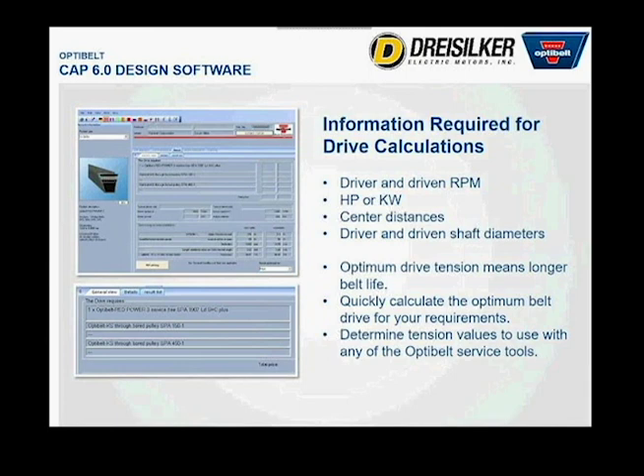Dreisilker's salesmen are able to do calculations for you. The biggest pieces of information they need are the driver and driven RPM, so your input and output, what your motor RPM is, typically 1800 or so, and what RPM your fan is running at, plus the amount of power being put through in horsepower or kilowatts. Then they need either center distances, or pulley sizes and the belt, and how many belts you have and what size they are.